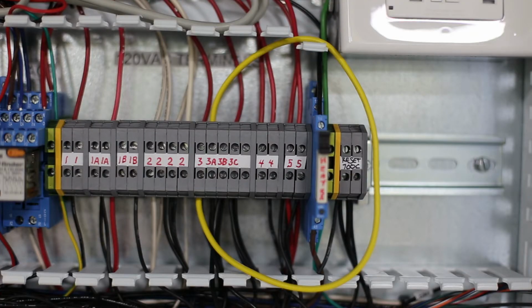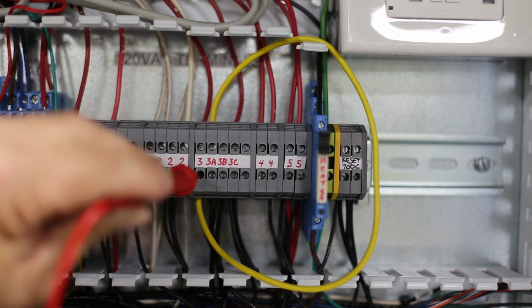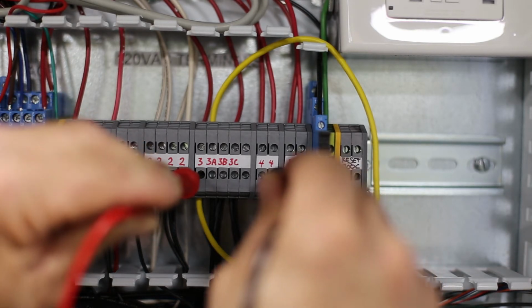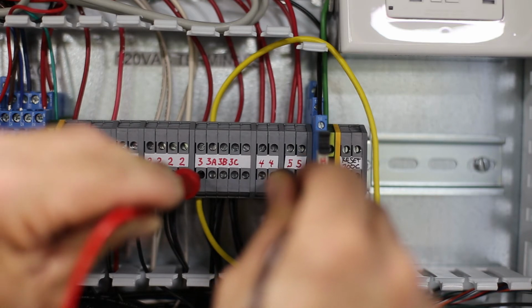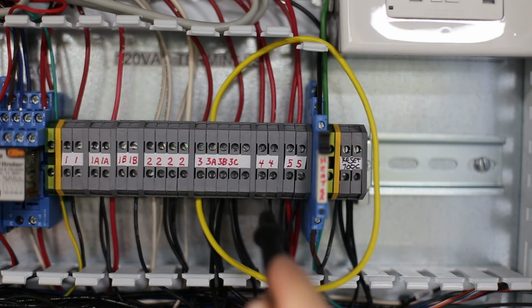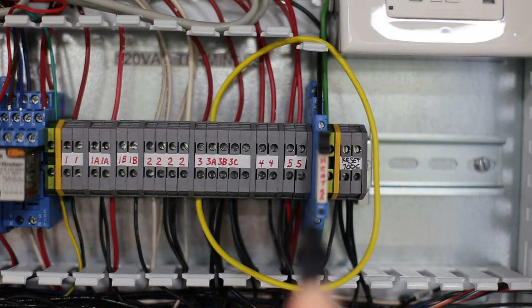The next step is the stop circuit. If you don't have the stop light on, you need to go and check ohms again between 3 and 4. If you have ohms between 3 and 4, that means that stop is working. If you don't have ohms between 3C and 4, we need to go and check that stop button or the contactor on the back side of the stop button on your console. Something in there is either loose or the contact is loose from the switch itself.